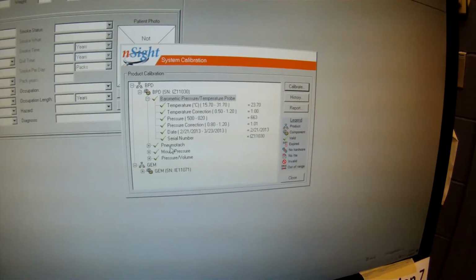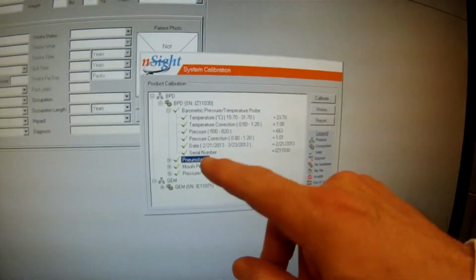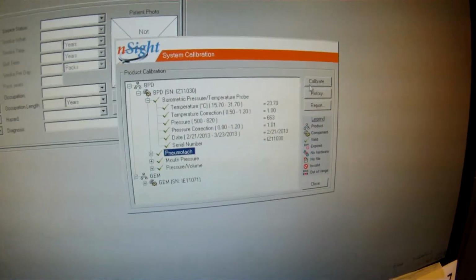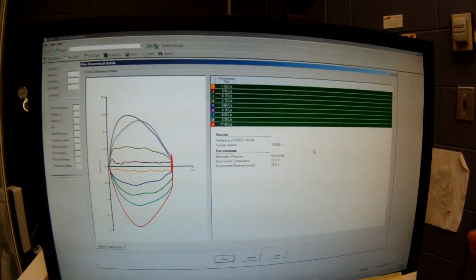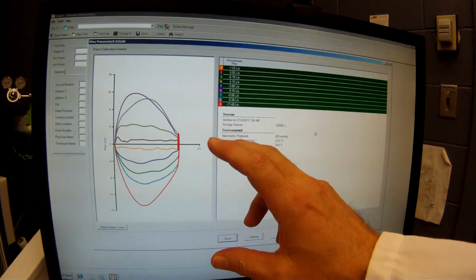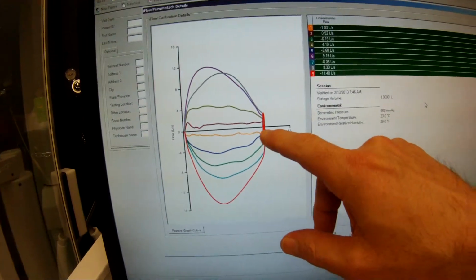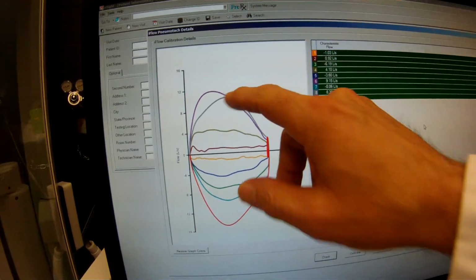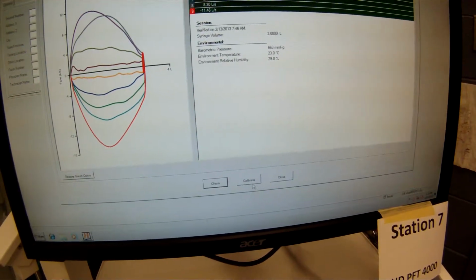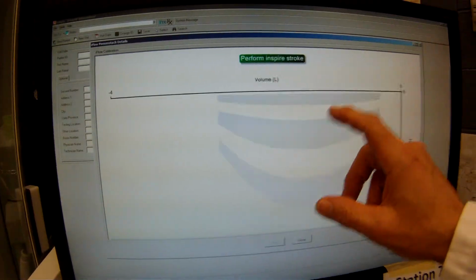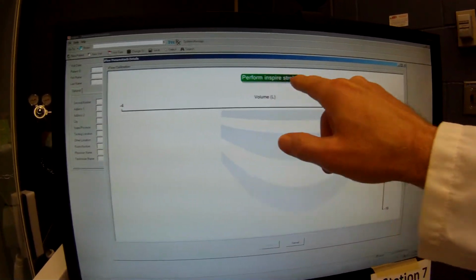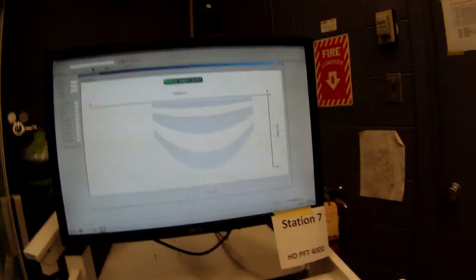All right, so now we're going to actually calibrate our pneumotach. So go up here and hit calibrate. Now it shows us one of the older calibrations that's been done. And from this you can see that it's very important to do low, medium, and high flow rate calibrations. All right. So click on calibrate. We're going to do a calibration here. We're going to use our 3-liter syringe. So we're going to continue on from that. Now this is going to indicate for us the desired flow. So we're going to perform an inspiratory stroke, and we're going to try to meet that inspiratory flow demand.